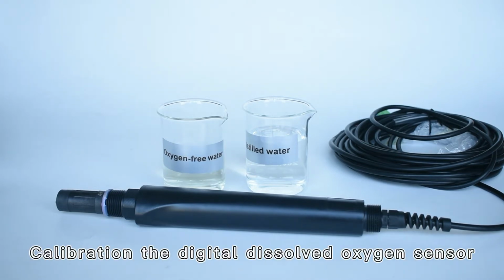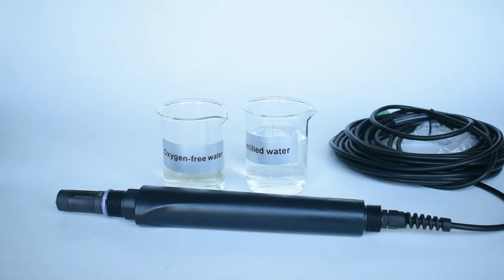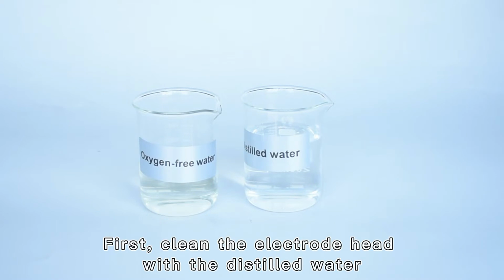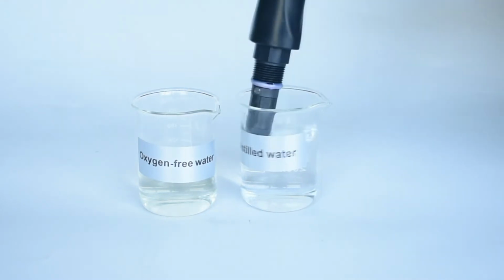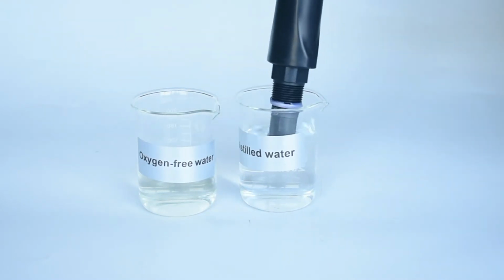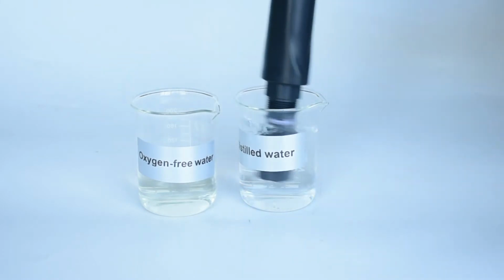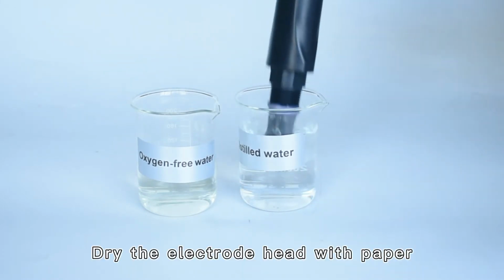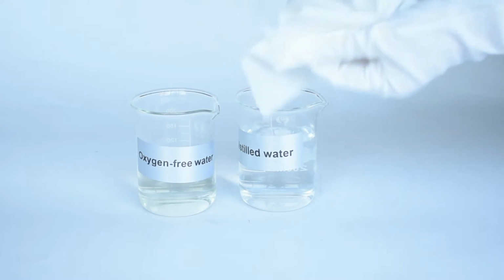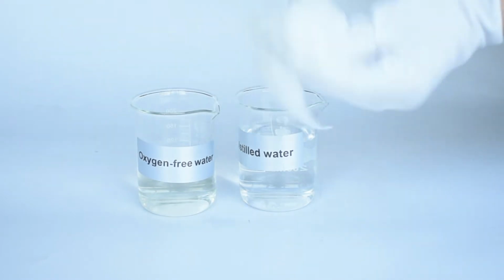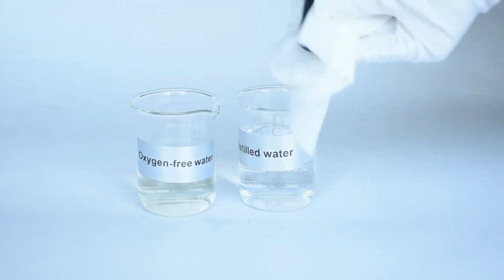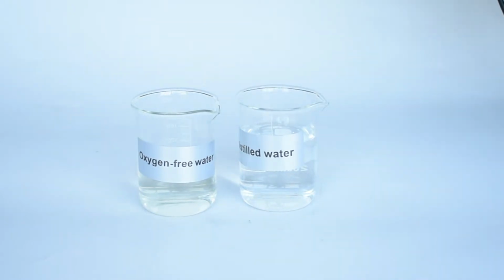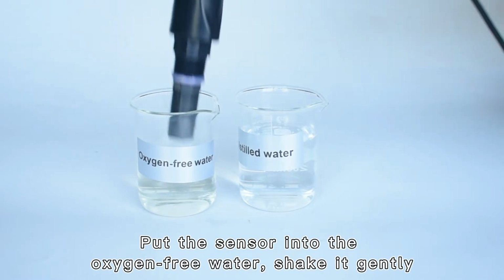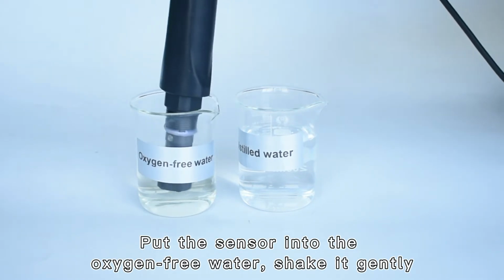Calibration of the digital dissolved oxygen sensor. First, clean the electrode head with distilled water. Dry the electrode head with paper. Put the sensor into the oxygen-free water, shake it gently.